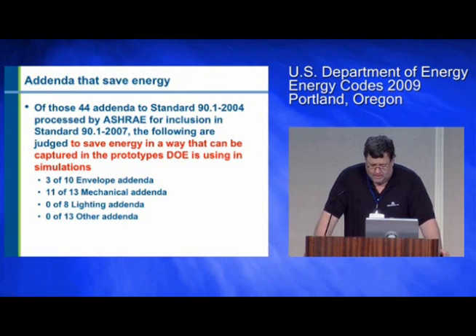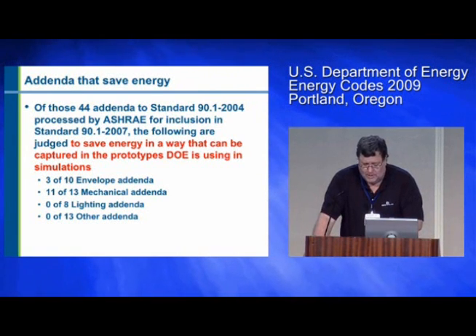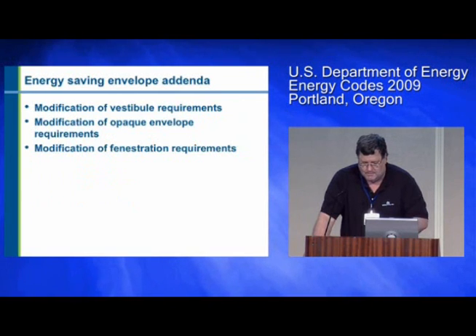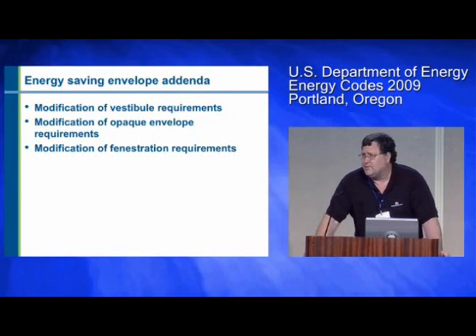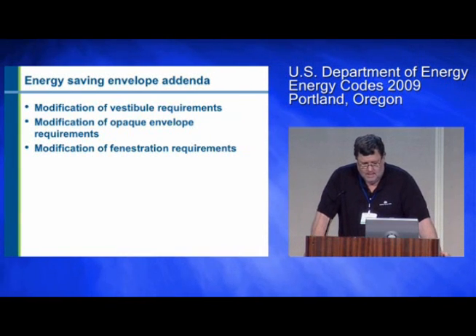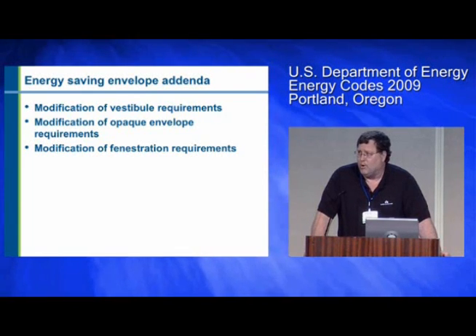Most of the mechanical addenda are going to achieve some energy savings. Most of the lighting addenda in this 90.1 2007 aren't a big deal, and none of the other addenda are either. So let me talk about the ones that we think are going to have some big impact. The 90.1 2007 has modified vestibule requirements. More buildings are going to be required to put vestibules in place. There's also some changes to the opaque envelope requirements and changes to the fenestration. Both of those have gotten more stringent as a general rule. Not for every building, not for every location, but as a general rule.